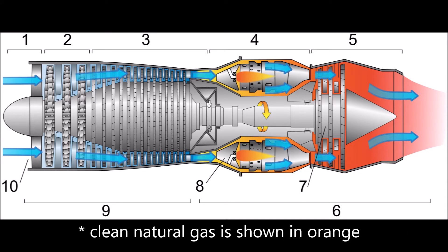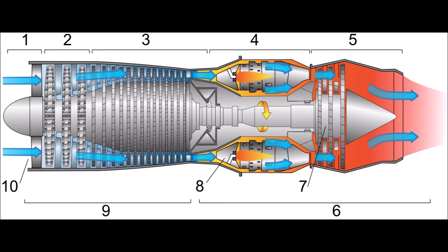Dry, low-NOx fuel combustion nozzles are more sensitive to the quality of gas. The fuel ring supplying the gas gets very cold due to pressure drop, so it's important to have the fuel gas above its dew point. This prevents liquid formation prior to combustion.